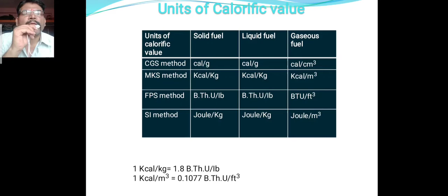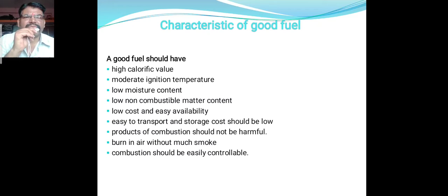Now the units of calorific value for solid, liquid, and gaseous fuels. In the MKS system, it is kilocalorie per kg for solids and also kilocalorie per kg for liquids, but for gas it is kilocalorie per meter cube, because gas is measured by volume while solid and liquid fuels are measured by mass. The SI unit is joules per kg for solid and liquid, and joules per meter cube for gas. 1 kilocalorie per kg is equal to 1.8 BTU per lb, and 1 kilocalorie per meter cube is equal to 0.1077 BTU per cubic feet. That is the unit of calorific value.